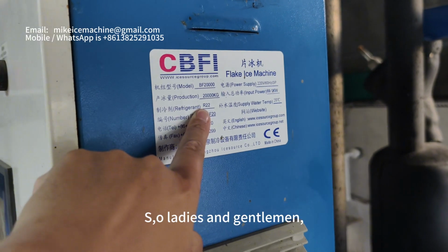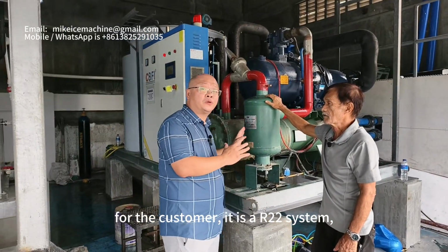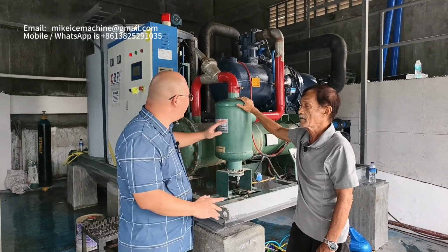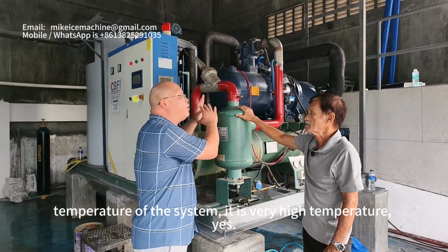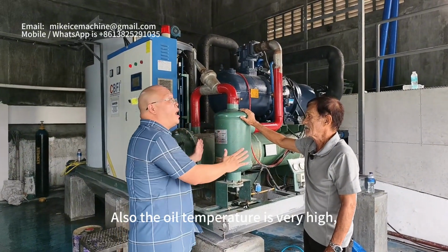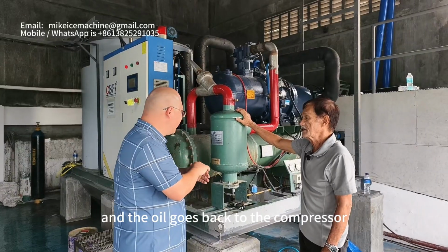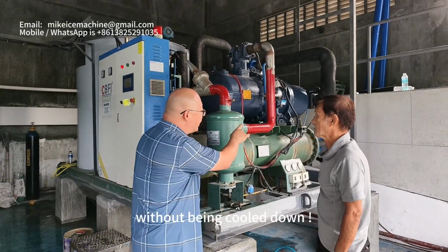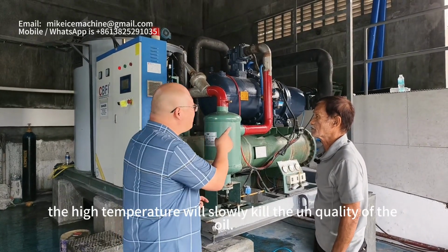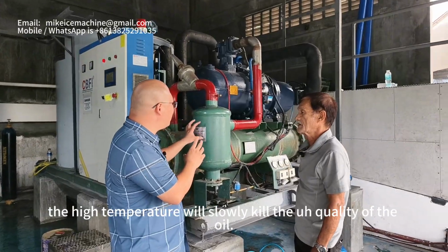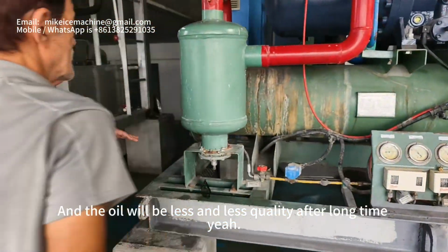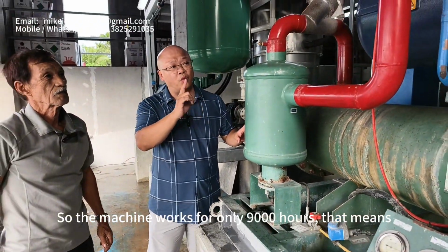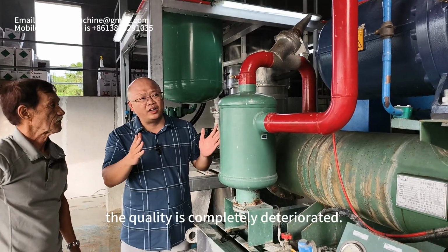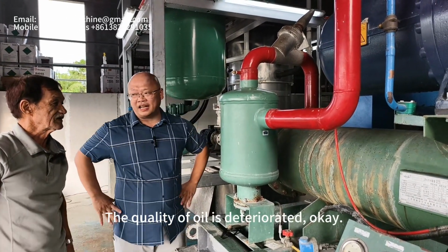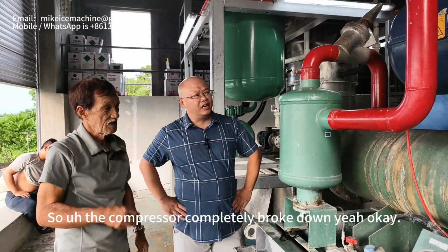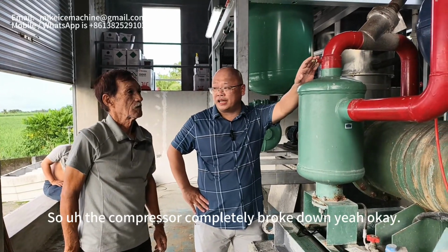So, ladies and gentlemen, the CBFI had a machine for the customer. It's an R22 system and it has no oil cooler. We all know that the discharge temperature of the system is very high. Also, the oil temperature is very high, almost over 100 degrees Celsius. And the oil goes back to the compressor without being cooled down. So the high temperature will slowly kill the quality of the oil, and the oil will be less and less quality after a long time. So the machine worked for only 9,000 hours. That means the quality deteriorated after 9,000 hours, and the compressor completely broke down.